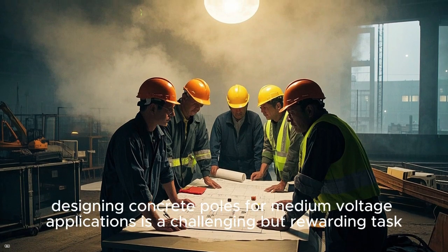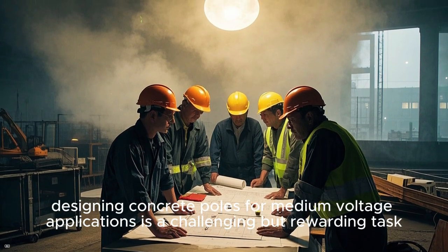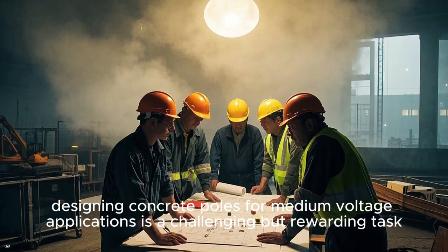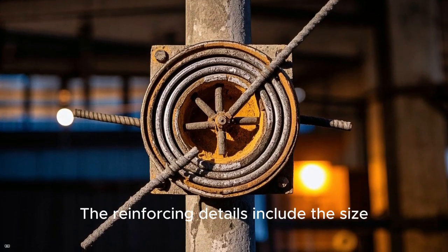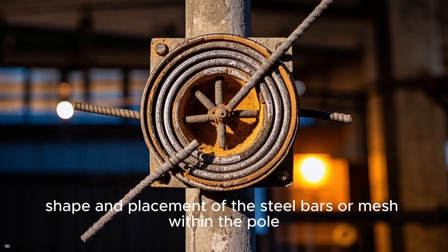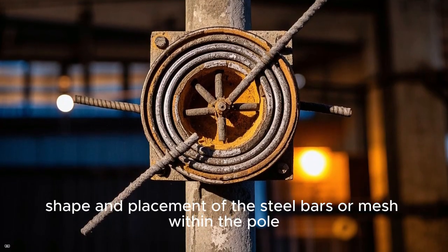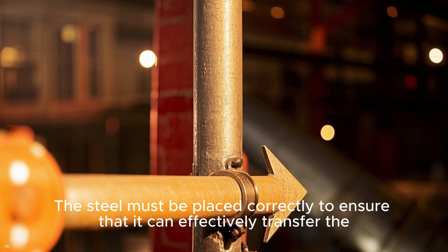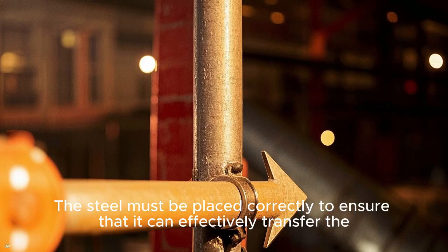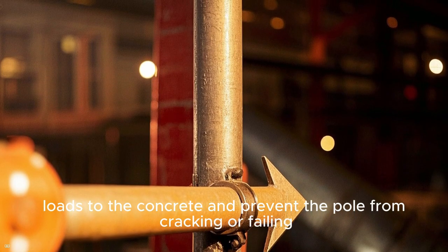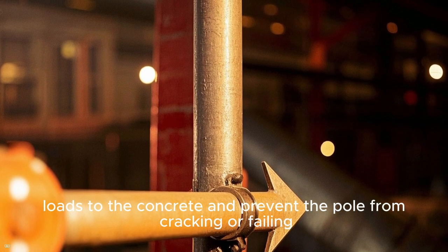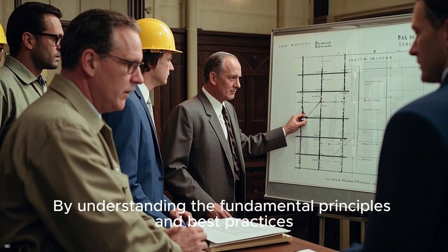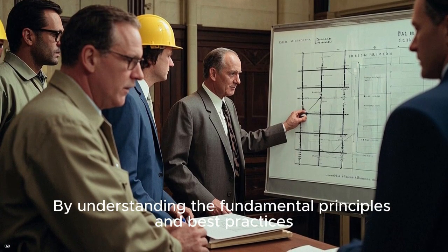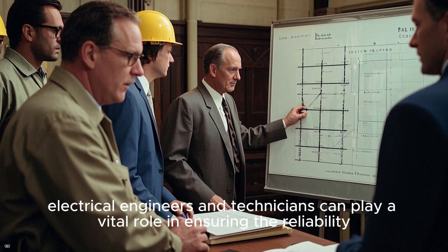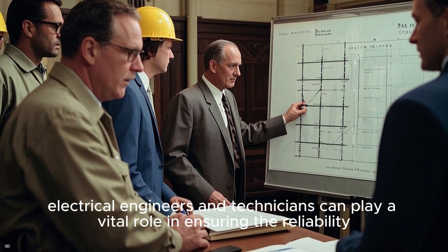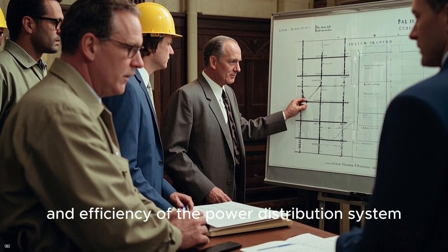Overall, designing concrete poles for medium voltage applications is a challenging but rewarding task. The reinforcing details include the size, shape, and placement of the steel bars or mesh within the pole. The steel must be placed correctly to ensure that it can effectively transfer the loads to the concrete and prevent the pole from cracking or failing. By understanding the fundamental principles and best practices, electrical engineers and technicians can play a vital role in ensuring the reliability and efficiency of the power distribution system.